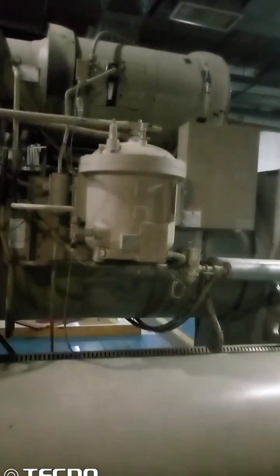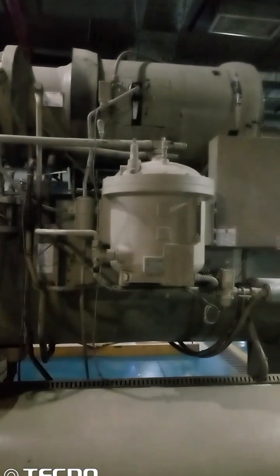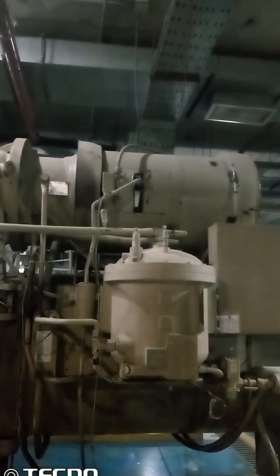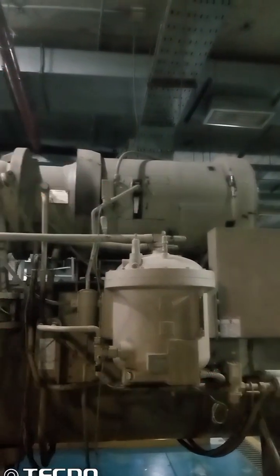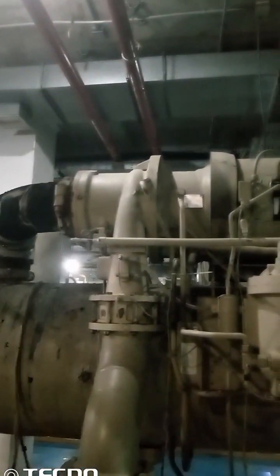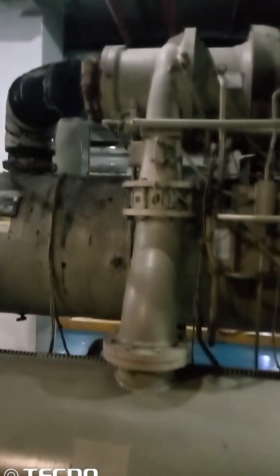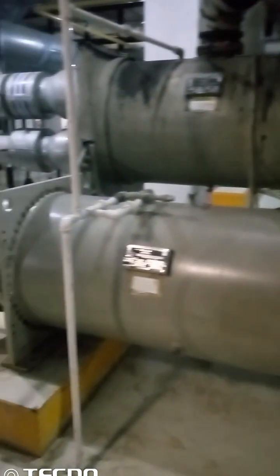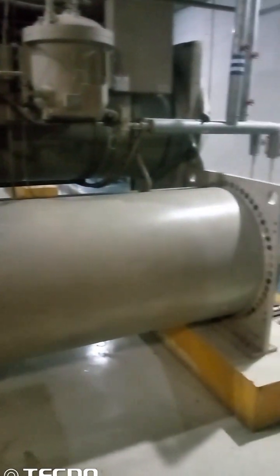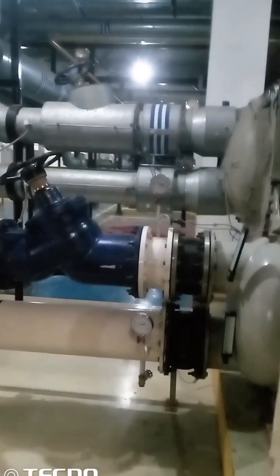First of all, at the top side of the chiller we have the compressor, and the compressor's job is to compress the refrigerant to high pressure and high temperature and send it to the condenser. The little drum beneath the compressor is the oil sump. And that's the discharge line of the compressor, through which vapor comes to the condenser's shell and is condensed by the cooling water from the cooling tower in the tubes of the condenser.